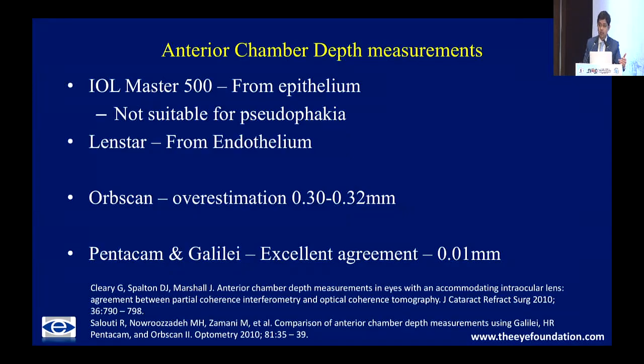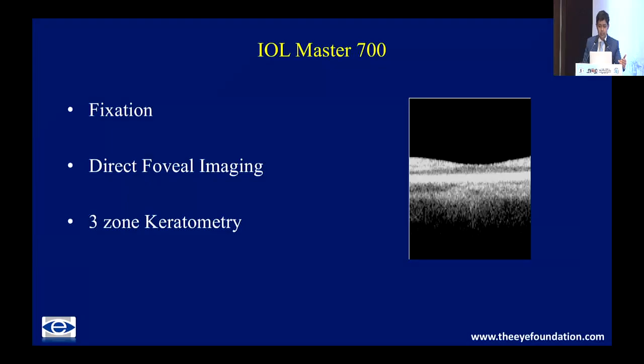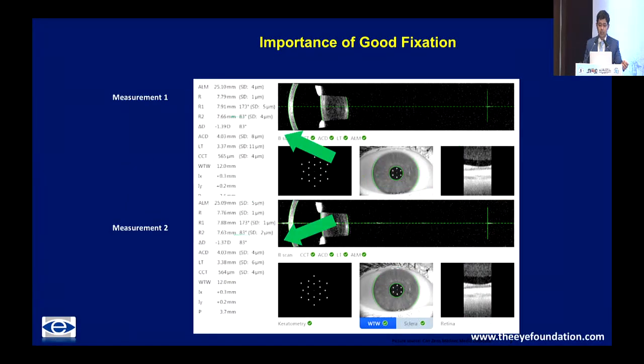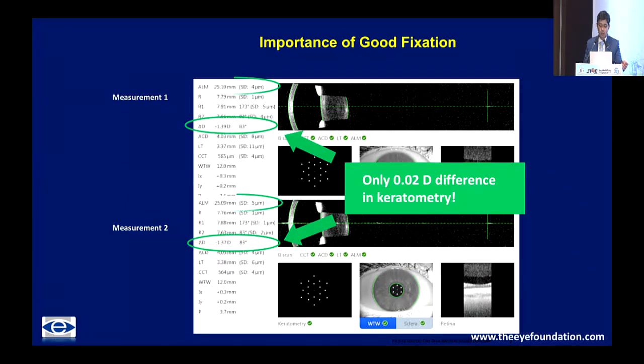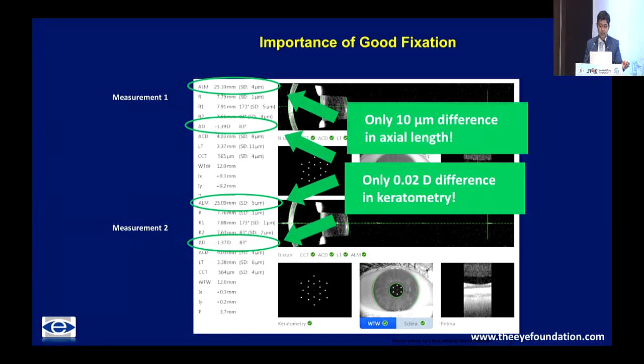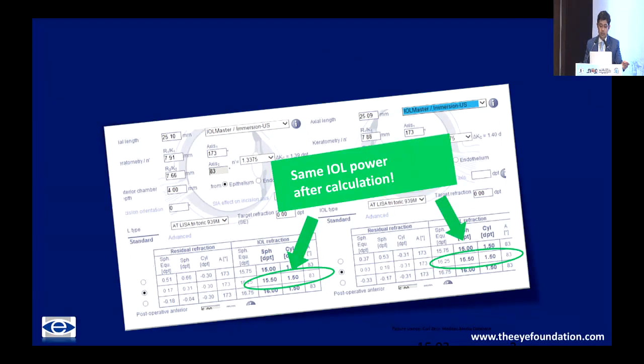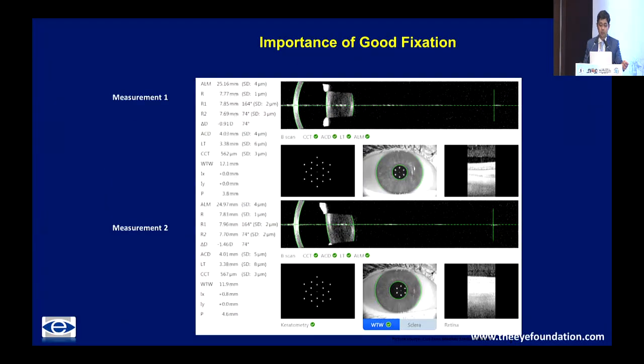IOL Master 700 has corrected that, and any of the swept source based biometry devices really give us a greater advantage because you have direct foveal imaging, which is now available. By directly looking at the fovea, we can tell whether the patient is fixating at the right point or not, and this really improves getting repeatable values. When you know that the patient is fixating correctly, your axial length and keratometry measurements are similar, and you also get a very similar and repeatable IOL power calculation.